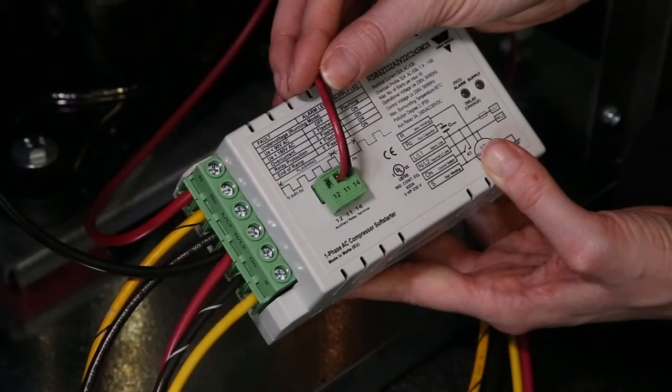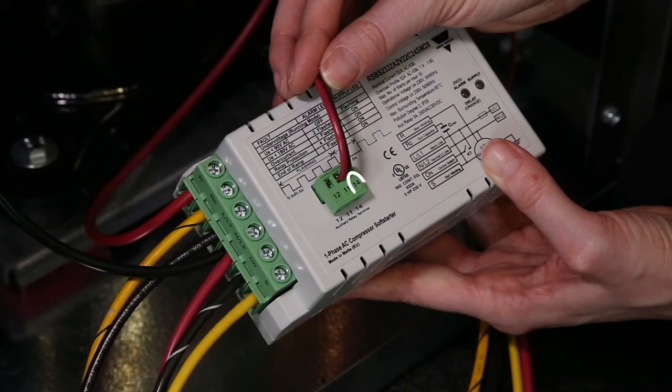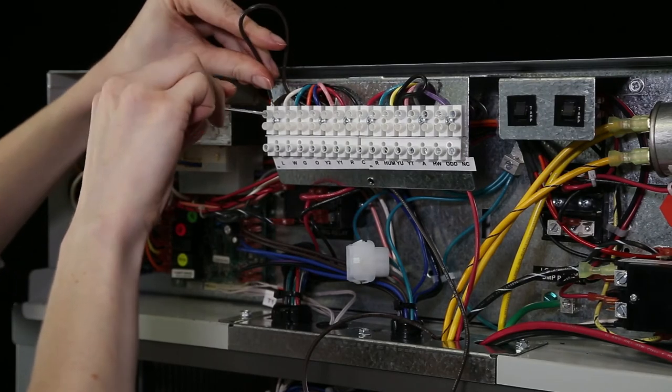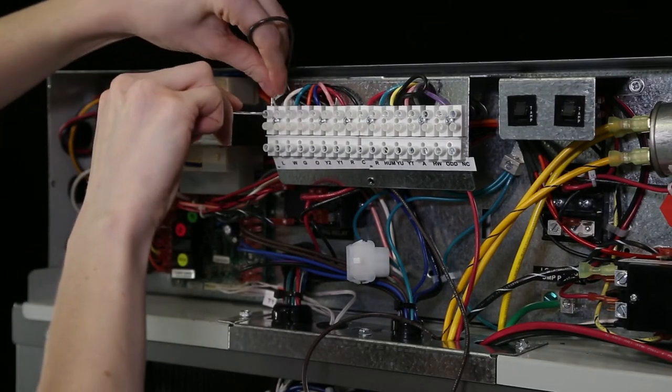Connect one end of the brown 18 gauge wire to terminal 14 on the auxiliary relay connector on the soft start module and the other end to the L terminal on the thermostat terminal strip in the control box.